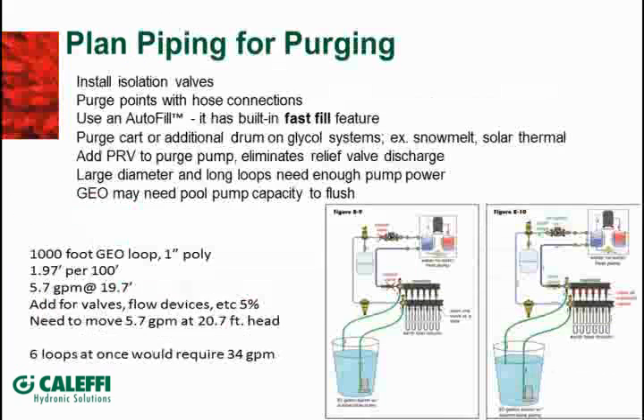Now, here's an example, I showed you this example a little bit earlier. Let's say we're going to flush and fill a geo loop system, and we've got a big 1-inch diameter, 1,000-foot loop there. We know we need about 5.76 gallons a minute flow rate to be able to push the air out of that, so that equates to about 19 feet of head. So again, we've got a pump here. Let's say we've got a large enough pump that you'd be able to flow through that loop and purge it out.